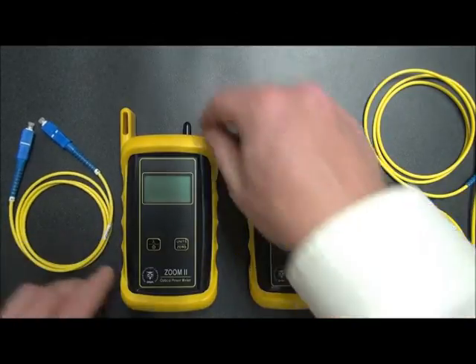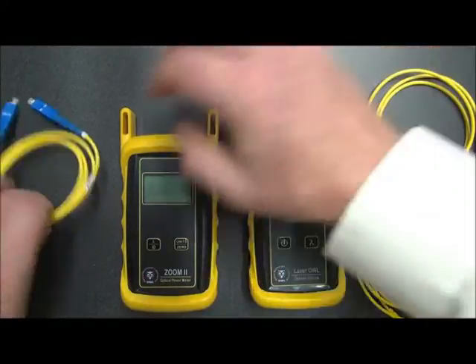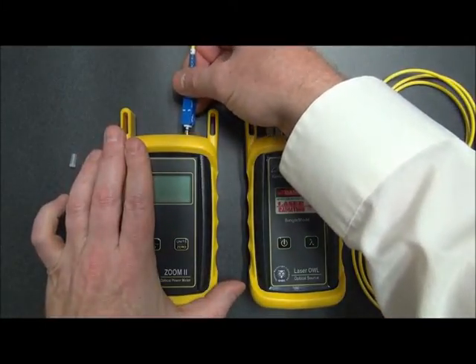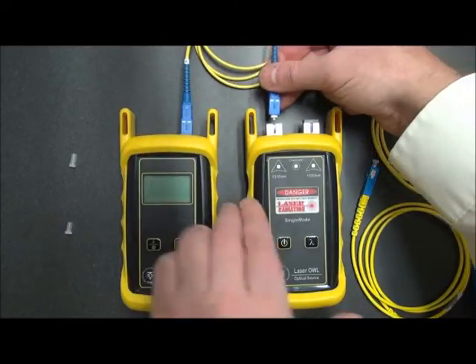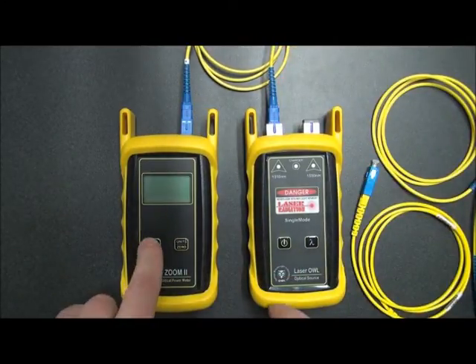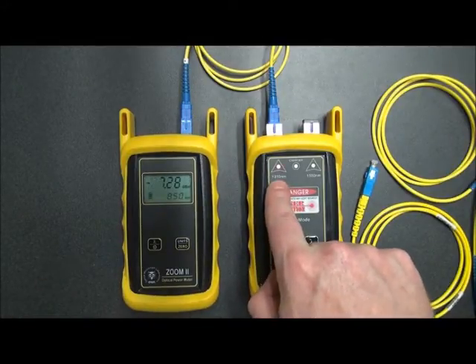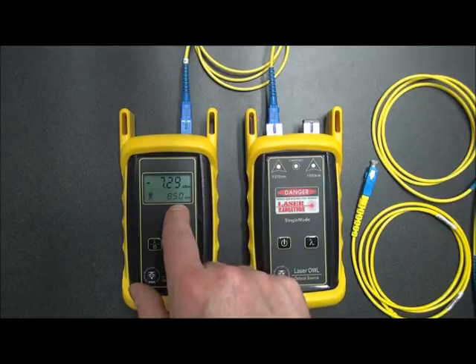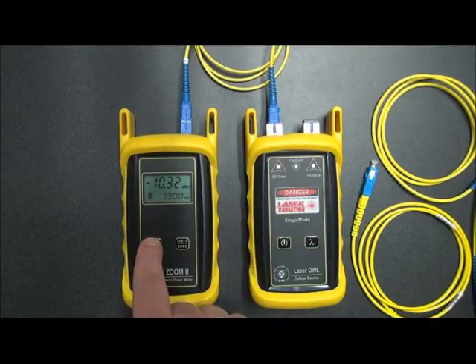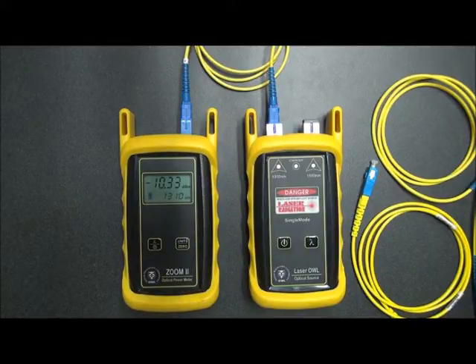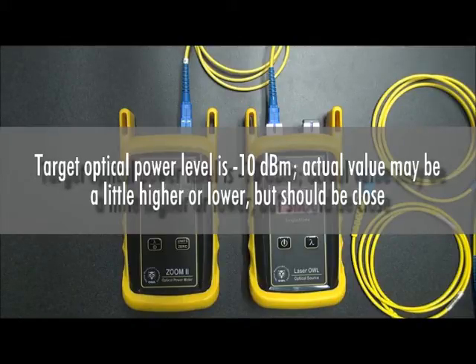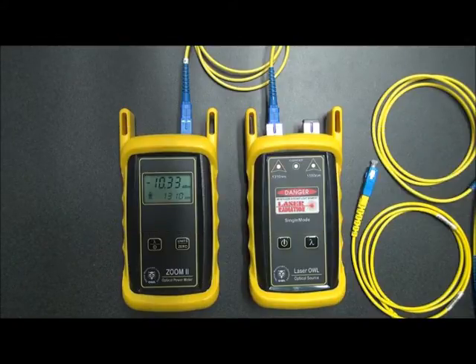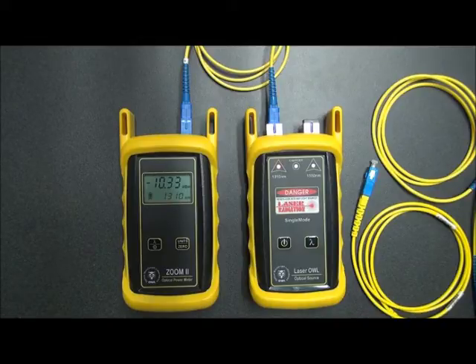The first thing we want to do is connect the cable we'll be using for the power meter side of the test into the 1310 nanometer port, then power on the units. The 1310 nanometer wavelength is lit by default, but the Zoom reads 850 nanometers, so we press the wavelength button until we see 1310. Our target value is roughly minus 10 dBm — this is where we calibrate our laser. The reading is about minus 10.4 or 10.3, which is okay to use.